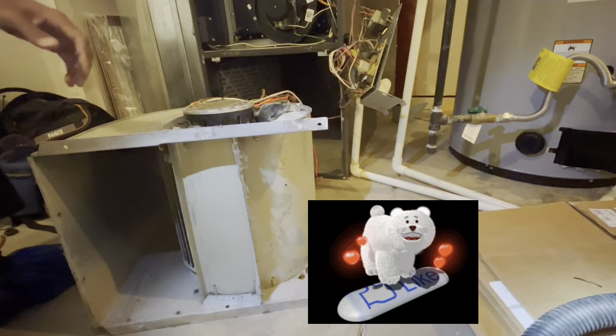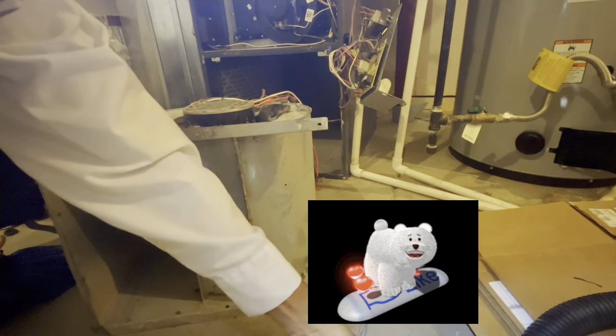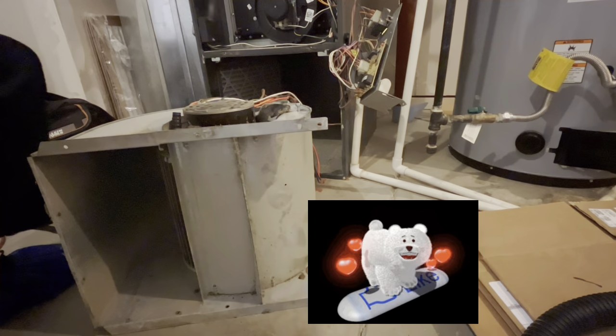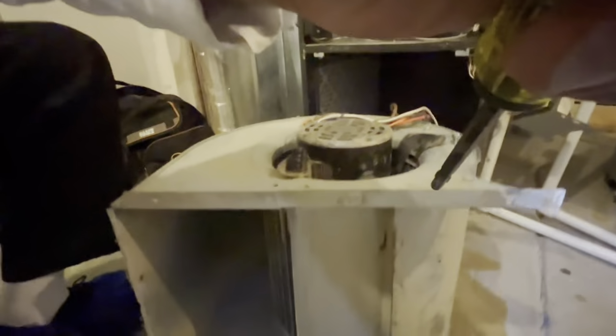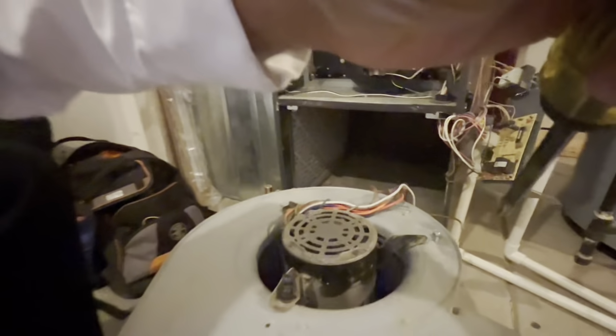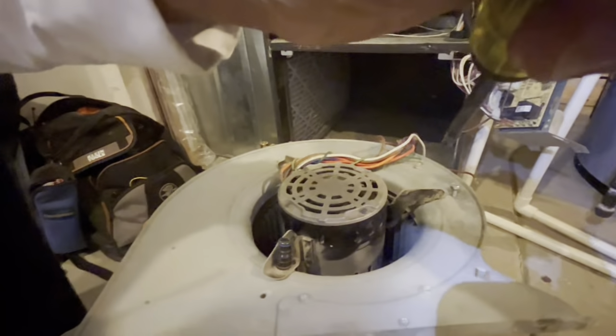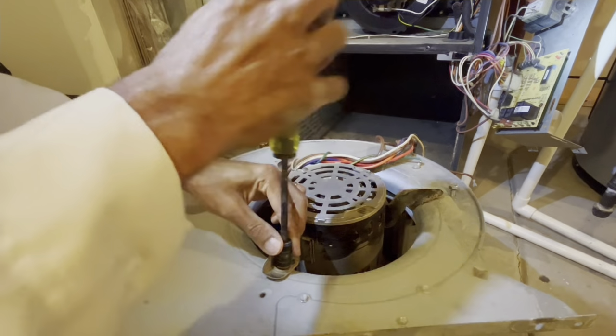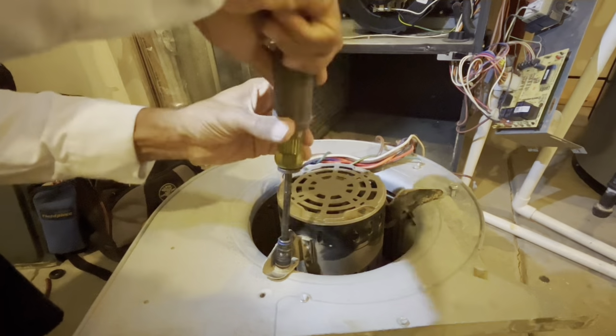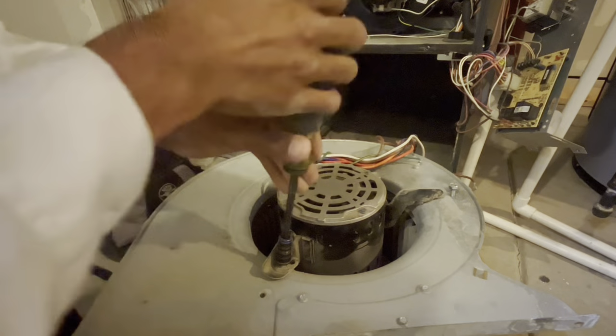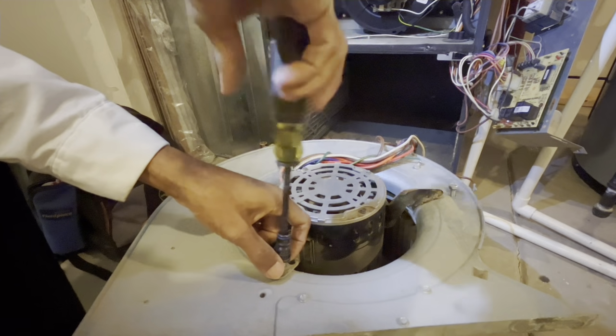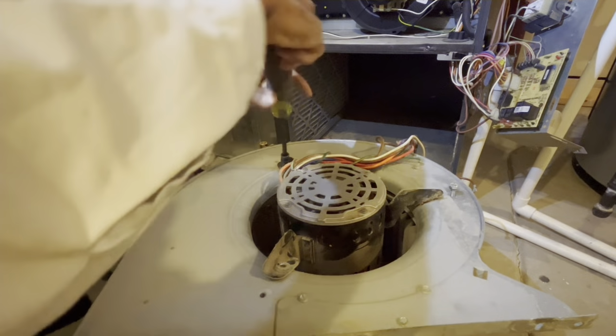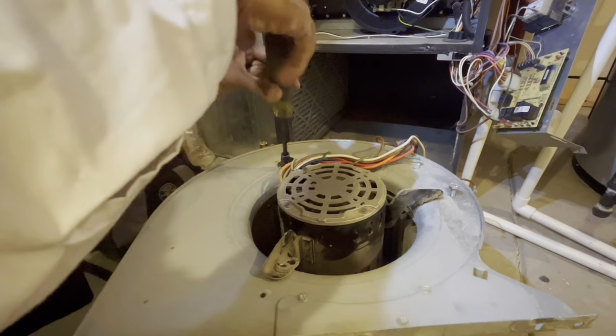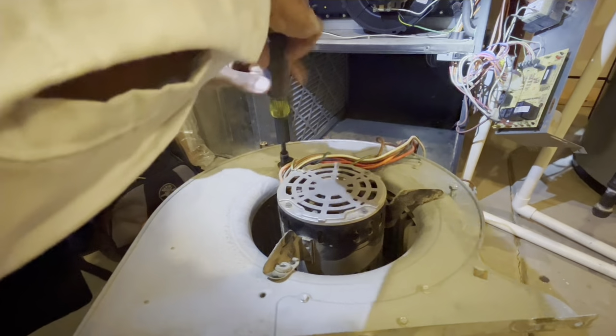So once I get it loose and I know the wheel is actually going to come loose, then I take all the screws off that mount the motor to the housing. Sometimes those are more like a 3/8 or 7/16, I believe. Let me get you in a little closer here so you can see what's going on. Basically I have a Klein screwdriver that has 6 different sizes, and with this one screwdriver you can basically take that whole furnace apart by hand. But it's good to have a drill too, an impact drill, to do what you need to do.